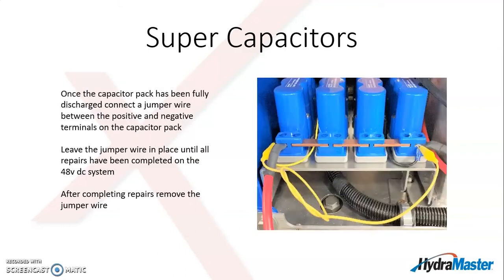Once the capacitor pack has been fully discharged, then you want to install that jumper wire between the positive and the negative terminals on the capacitor pack, and then leave that jumper wire in place until you've completed any work that you're doing on the 48 volt side of the system. And then after completing the repairs, just remove the jumper wire and the capacitors can be charged up again.